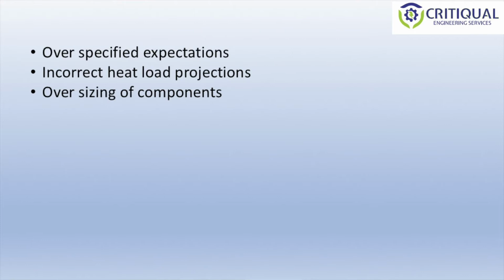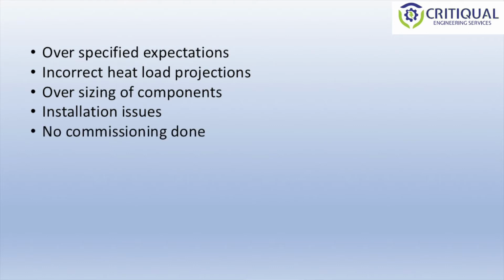The design brief may specify impractical expectations. The heat load projections may be wrong. The designer or consultant oversizes the equipment to cater for redundancy. The equipment may not be installed with standard engineering practices. And finally, the plant may not be commissioned, or commissioned by the installing agency, and everyone knows where that practice can take us.